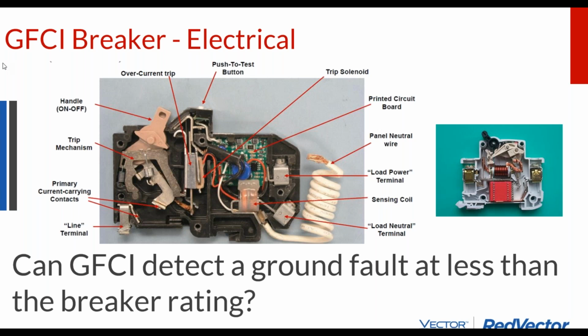So let's talk about ground faults and ground fault breakers and breakers in general. So how does a breaker work? Well, when you put 20 amps of load through a standard breaker, if you put more than that through that conductor and allow it to continue uninterrupted, if you overcharge a cable beyond what its ampacity is rated for, it'll start to heat up. And when it heats up, it's gonna smolder. The way that a breaker works is there's this coil inside the breaker that, when the electricity begins to heat up, expands and literally pulls the breaker open, and that interrupts the electricity and everything cools down, and it prevents your conductors from burning up.